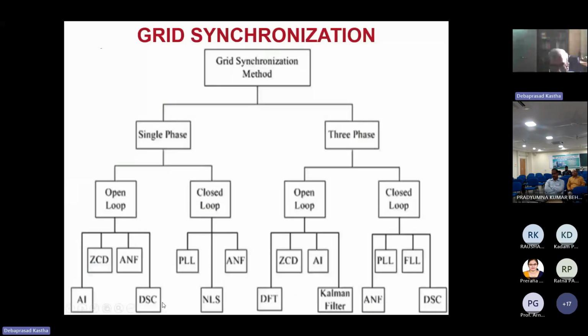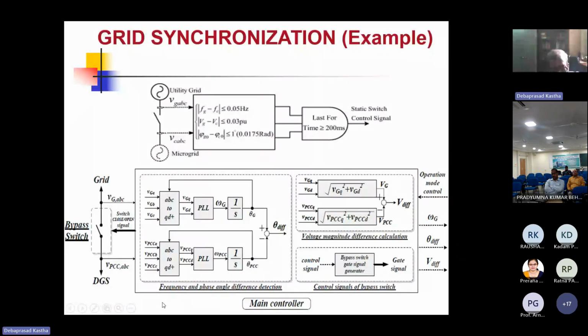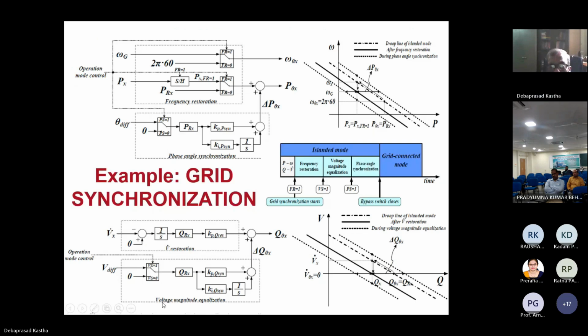There are many methods that have been discussed in the literature for synchronization. This is one of them. Basically, you will have to sense both the grid voltage and the microgrid side voltage, and make sure that the voltage magnitudes, frequency, and phases match before you close the synchronization switch. There are many ways of doing it. This block diagram shows one. This is a continuation of the same thing. This shows how these differences are mitigated.